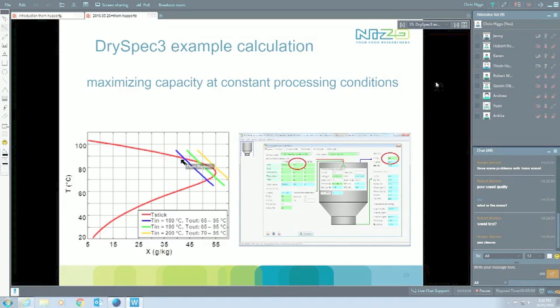We can start looking as well, if we increase inlet by 20 degrees and increase the outlet a bit too, we're actually going outside our stickiness zone. We run very big risks there of fouling of the dryer, very short run times, all these kinds of things, so we don't want to be there.